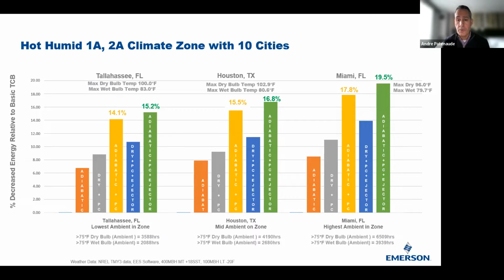So that's really important because if you don't have an adiabatic gas cooler, you can be operating in supercritical operation 6,500 hours a year. So how do you mitigate that? That's what this is all about, right? Trying to mitigate systems from operating in supercritical or transcritical mode. And it varies from climate to climate, depending on humidity and temperature, of course. So if we take a look at Miami, because it's the hottest, it has the most hours of operation in transcritical mode.